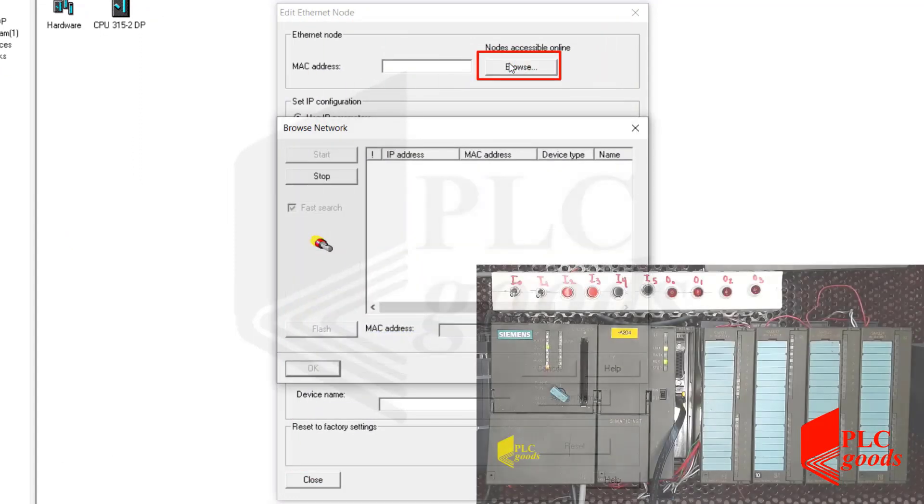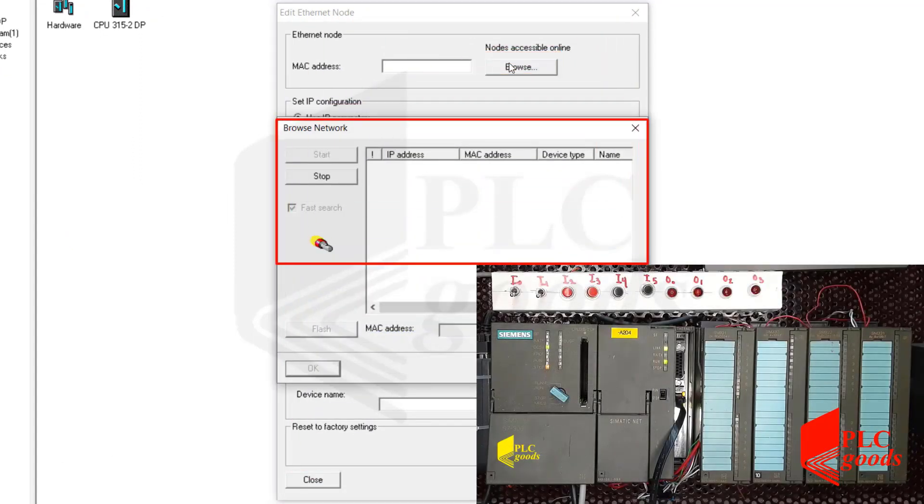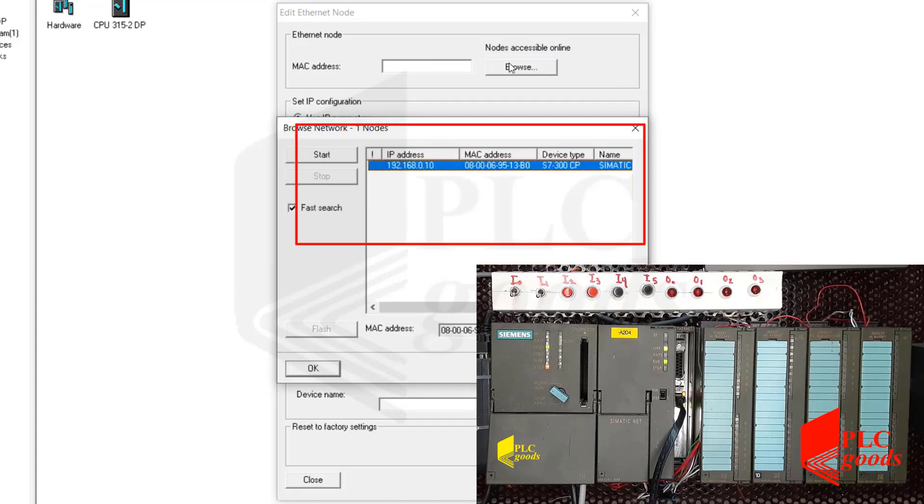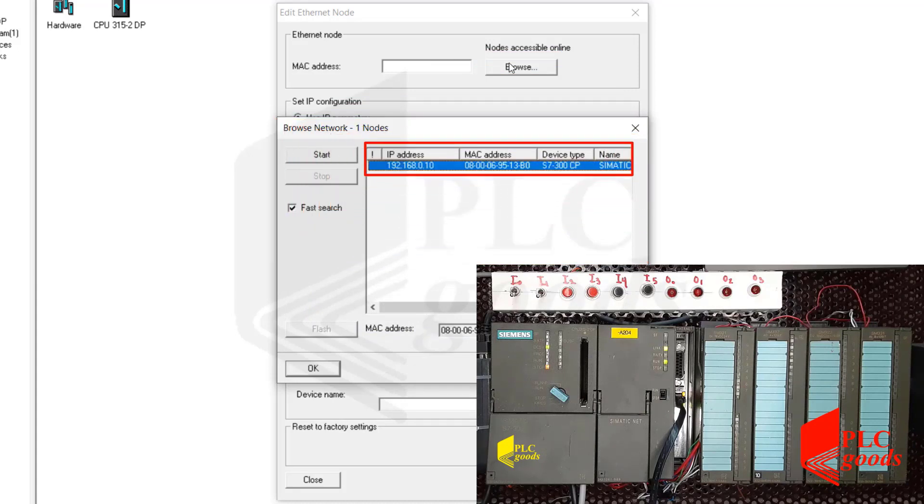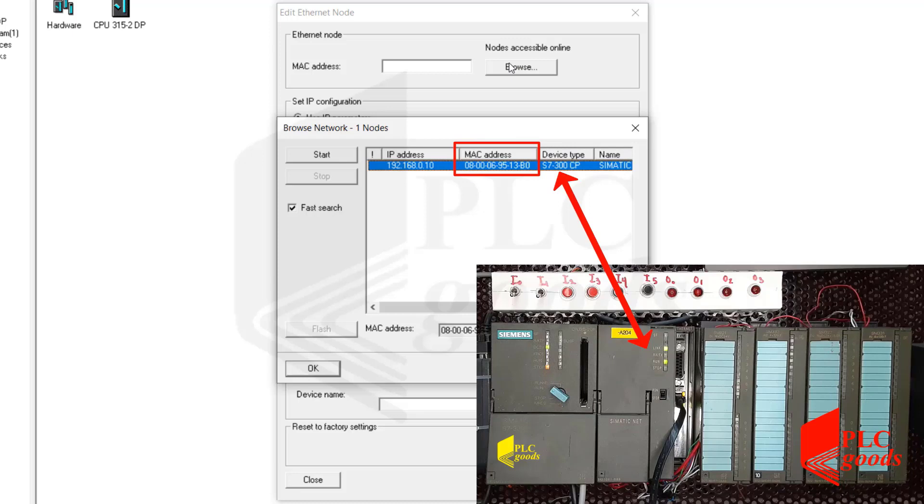Now let's open the PLC menu and click on the edit Ethernet node option. In this window, by clicking on the browse item, you can view the devices which are connected to my computer. As you can see, it's my network card which is installed between my CPU and signal modules.